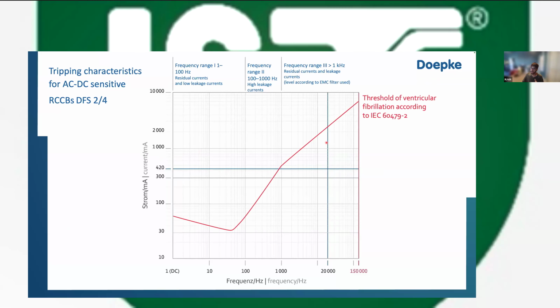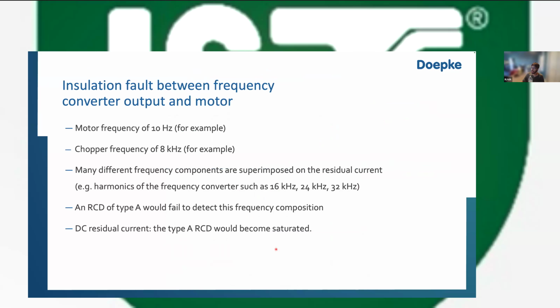See, the key thing is what is the relationship between frequency and electric shock? There's a standard called IEC 60479. It's prepared by a group in IEC TC 64 called Working Group 4. I was involved. And this shows that as the frequency increases, the threshold for the amount of current that can cause ventricular fibrillation, or your heartbeat to stop, in the event of electric shock also increases. And you need to make sure that the characteristic of the RCD that you are choosing also follows this pattern. So in this particular case, this RCD is disconnecting before this threshold of ventricular fibrillation. And crucially, this RCD has to be able to operate for all bands of frequency that the elevator may generate due to the operation of the chopper.